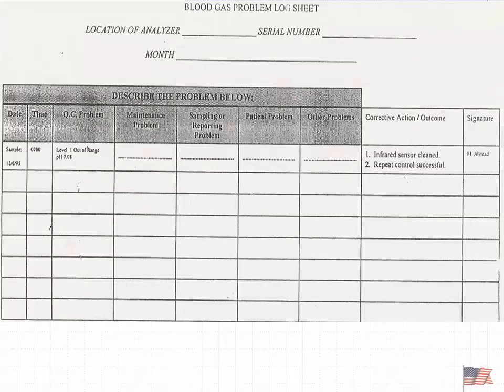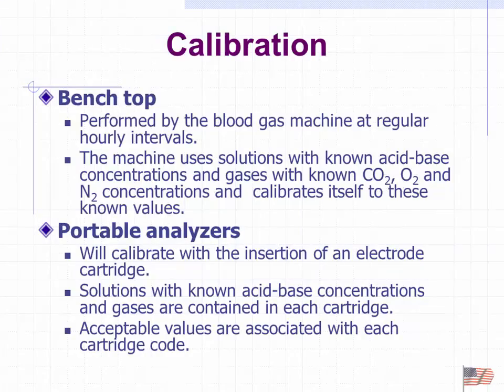And if we do any maintenance or any repair or any other involved process, we're going to document it so that we have a log of everything that we're doing to that machine. It's kind of like your car. You hopefully have a file that says when was the last time the oil was changed, so you know it's time. You guys do know that you need to change the oil, right? So with the bench top, those are done at regular intervals, and it also goes ahead and, using some known gases and some known solution, generates some calibration values and calibrates itself. With the portable analyzer, we said it's inside that cartridge. So every time you pop a cartridge in, it goes ahead and calibrates itself, and then verifies that it's properly functioning.